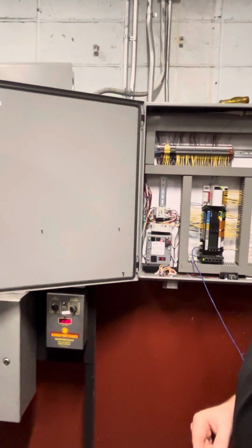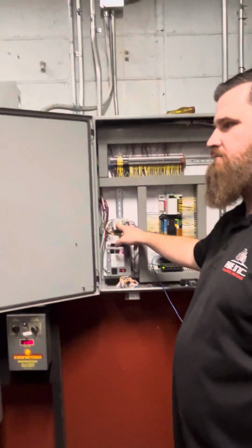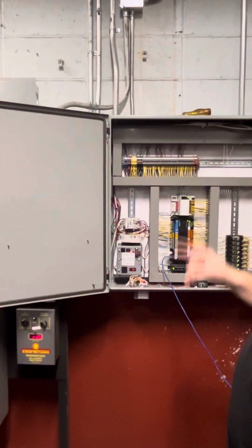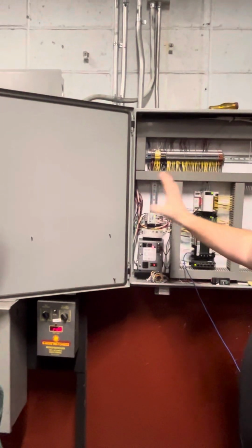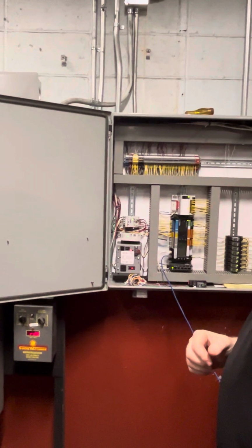The glass break shutdowns to all three boilers tie back in directly to here. If the glass break trips, we shut our enables off. If the CO2 goes off, it all triggers off of this one relay, gives me a signal, and sends everything over to those three boilers to shut down.